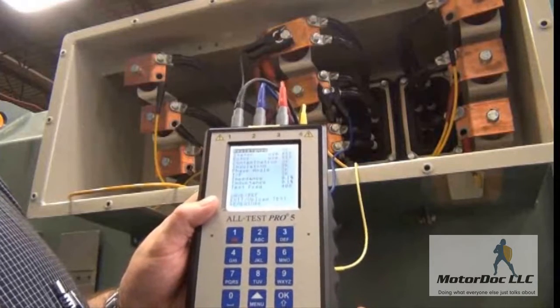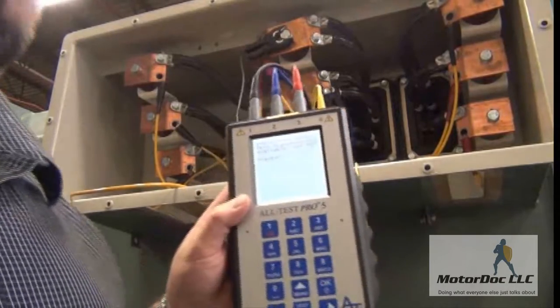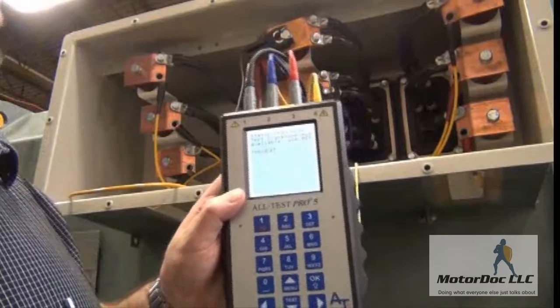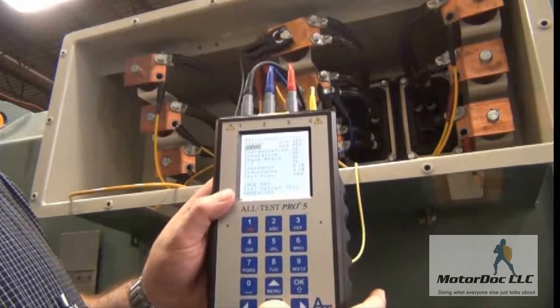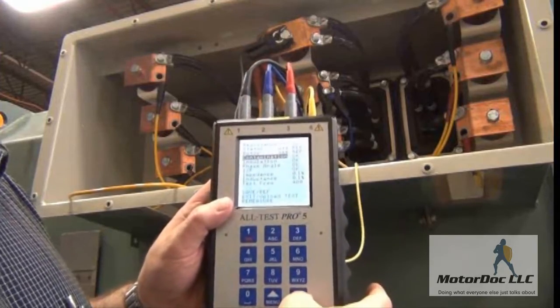I press OK again and come down here. It says use reference for these — there's TVS data, which I'll also describe in another video. Let's go ahead and back. Contamination: it says OK, meaning there's no contamination. This allows me to look at the dissipation factor and capacitance tests.